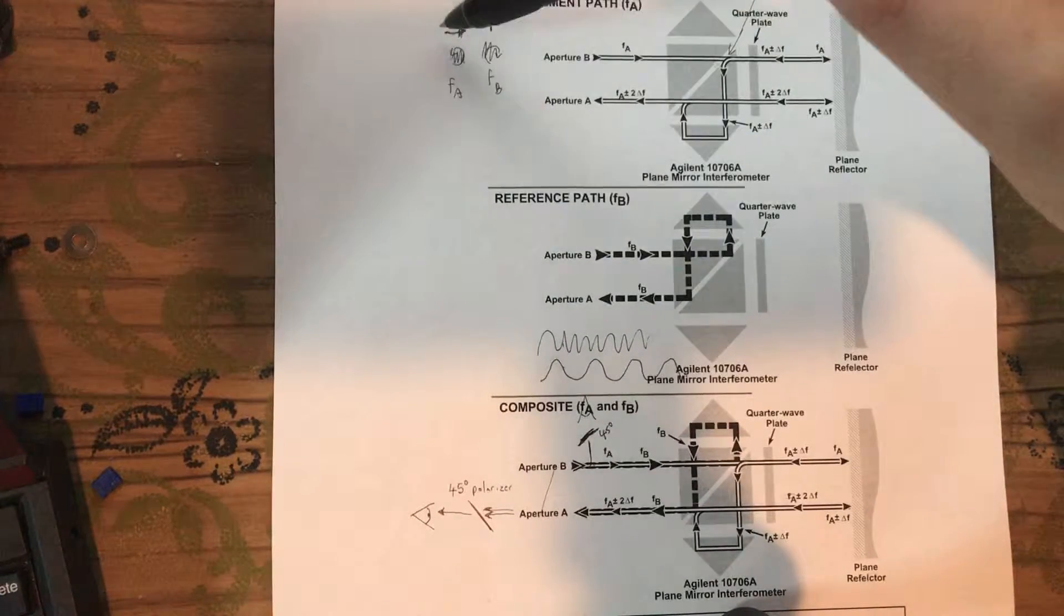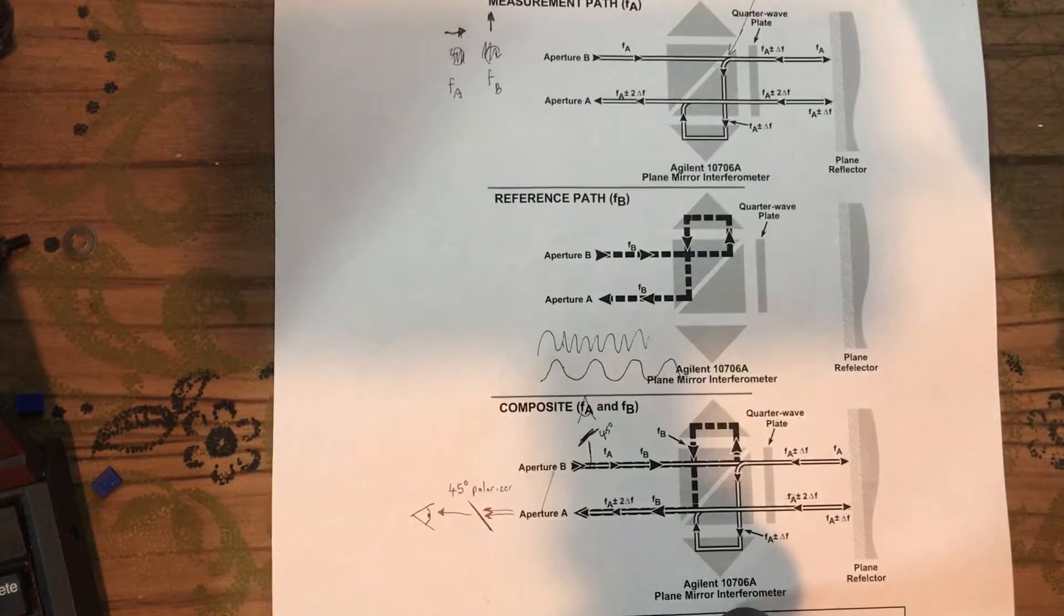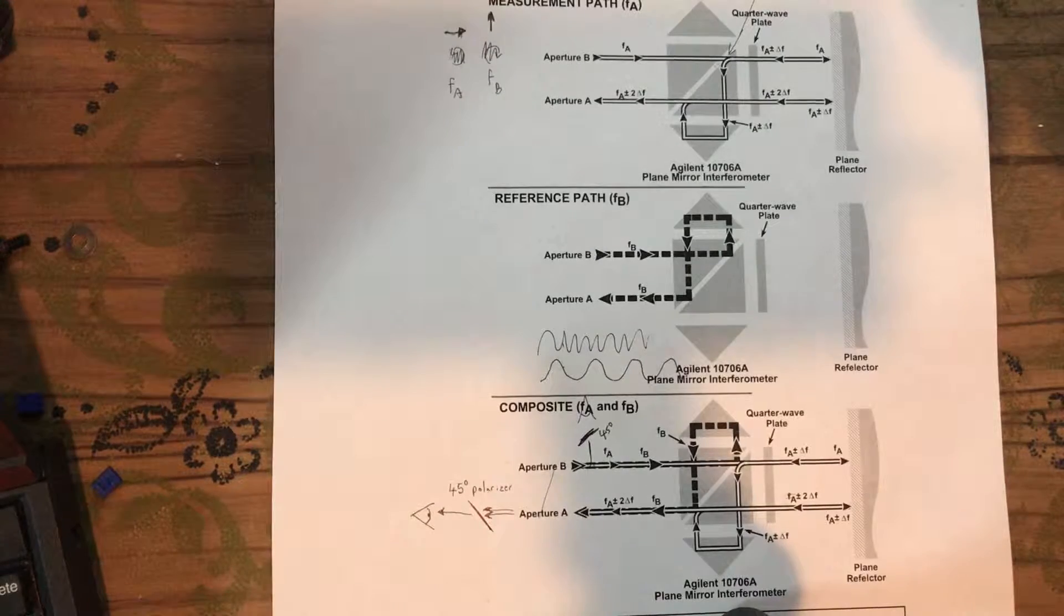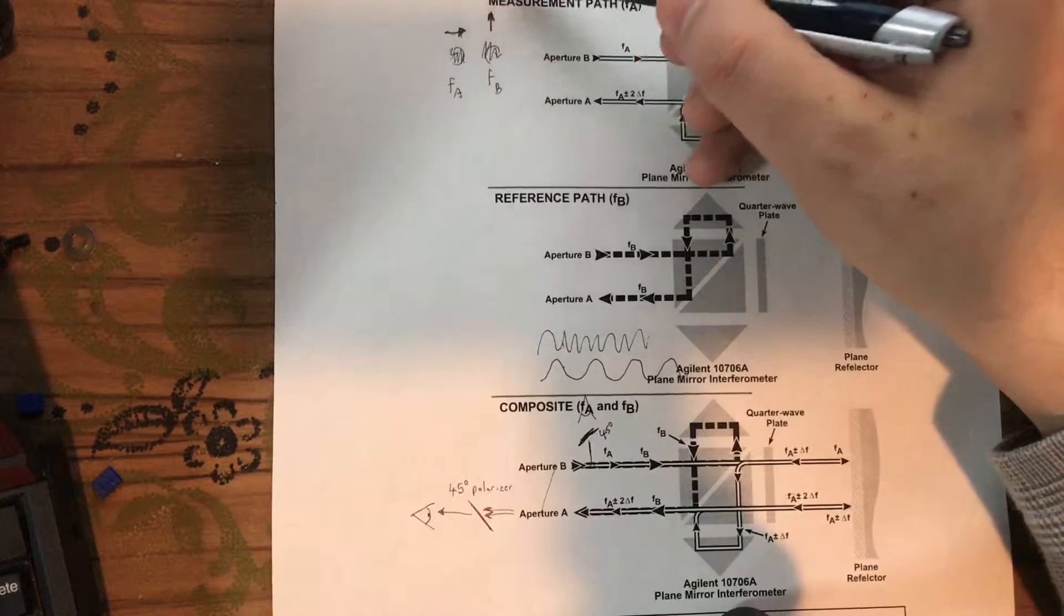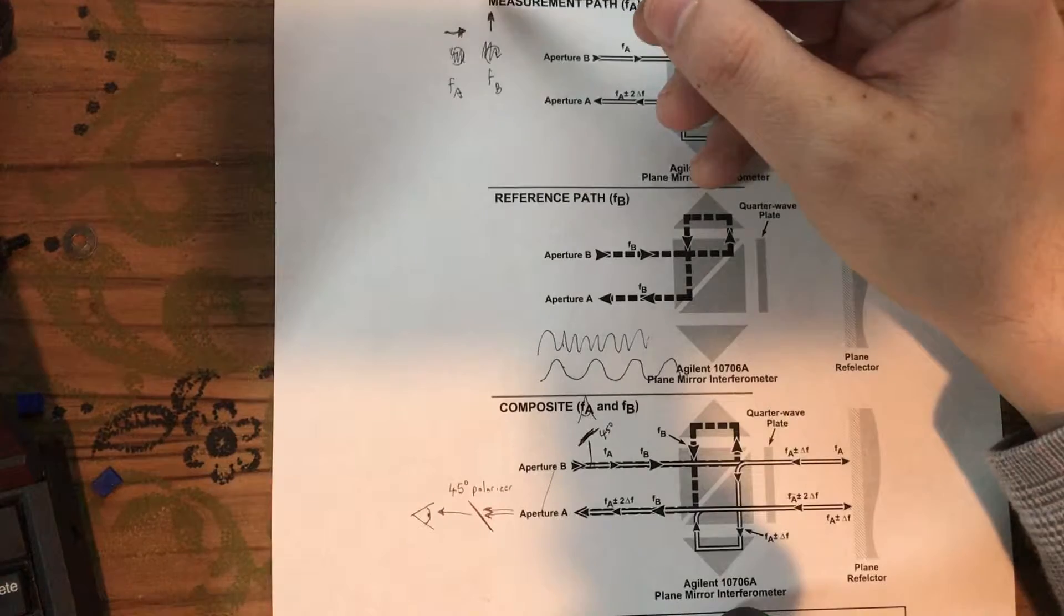First of all, you have this laser head. The laser head is not a normal laser head - it's a helium neon laser head which uses a Zeeman effect to generate two separate frequencies of light at the same time. These two frequencies are very nearly the same but they're a tiny bit different, about two megahertz apart.